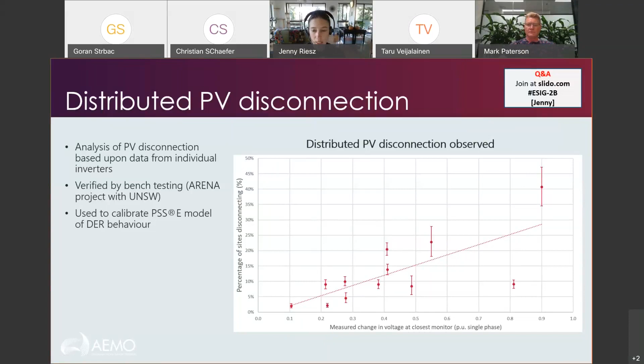What we found in incorporating all of that behaviour into our models is that if we have a severe but credible fault at certain locations in the grid, that can lead to significant disconnection of distributed PV. And when the PV levels are small, you actually see load disconnection as well, and the load disconnection will usually be larger than the amount of PV disconnection. But as the level of distributed PV increases, we see much more PV tripping off than load. So it becomes a net generation contingency. And importantly, this can happen in association with the loss of a generating unit. So you can have a certain kind of fault that disconnects that generating unit and will also disconnect a large amount of PV. So it's adding on to our largest credible contingency that we need to manage. And that has all sorts of flow-on effects for power system frequency management and so on.